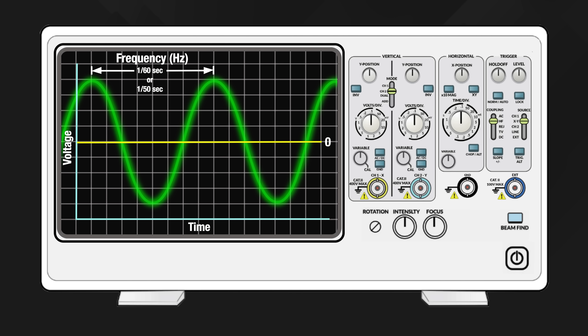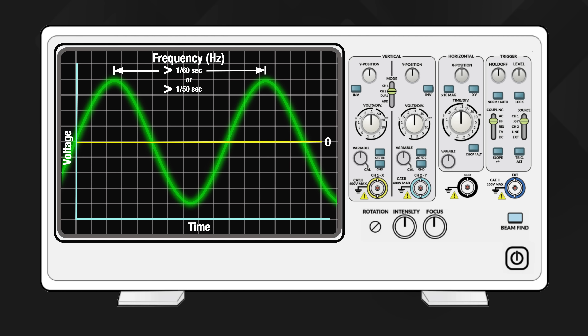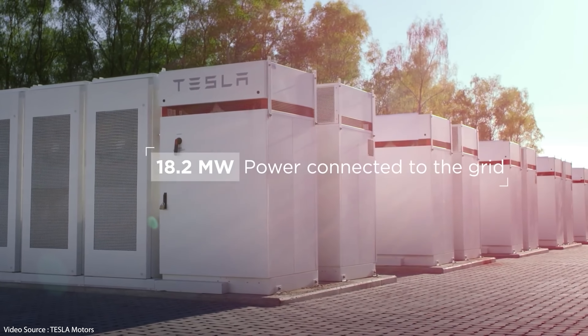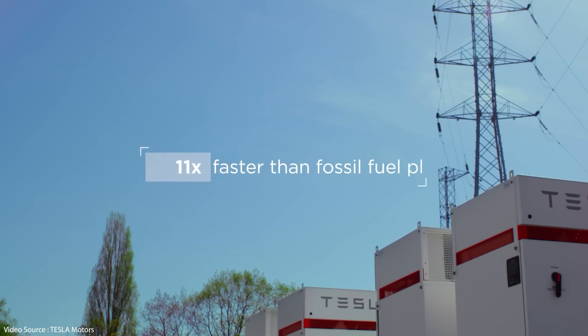Frequency is a function of the speed that the turbines are turning, but it's also a function of energy demand on the grid, which has to be precisely matched by supply in real time. If demand spikes higher than supply, the line frequency will drop — and if it deviates too far below 60 hertz in countries like the US, or 50 hertz in other parts of the world, there's a risk of brownouts or even complete system collapse. When renewables like wind and solar came along, they posed an additional challenge for grid operators with their extremely variable power outputs and intermittency. The most widely employed solution is to use energy storage like grid-scale lithium-ion batteries, which can respond instantly to variations in grid frequency. But some clever engineers realised they could in theory build standalone flywheels that could emulate the useful inertia characteristics of the old fossil-fuel-driven turbines that were being replaced.